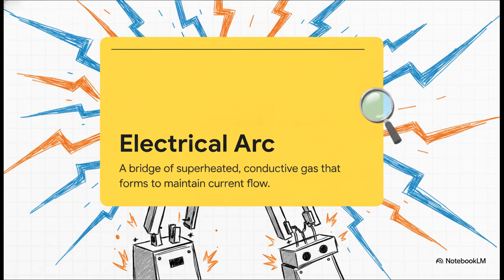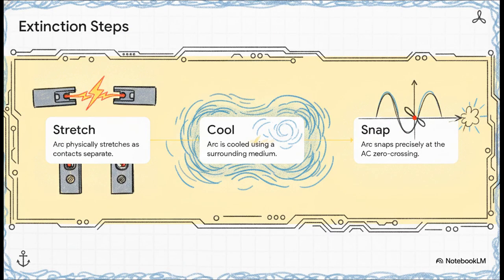Picture it almost like a living entity, a bridge of superheated, highly conductive gas that wants absolutely nothing more than to survive the interruption. It's violent, it's incredibly hot, and it is the absolute enemy of a safe electrical break. So how do we actually kill it? Extinction is a very specific physical process. First, the breaker physically stretches the arc. Second, it cools it down using a surrounding medium. But the real magic? That happens at step 3.